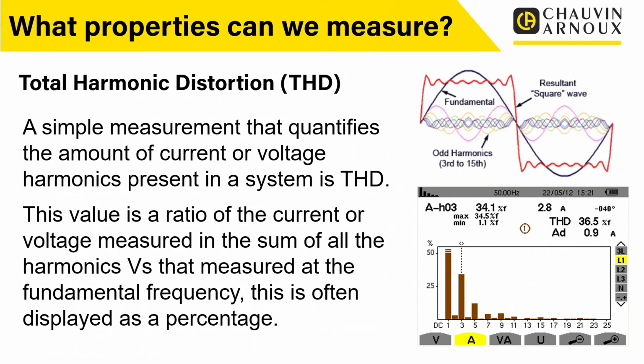And you can see on the graph on the right here, or the display on the right, we're actually measuring current there. So we're talking about current harmonics, and you can see there that we've got quite high 3rd, 5th, 7th, 9th harmonic content in there, and the actual THD is measured there at 36.5%. So that's quite a lot compared to the fundamental. Obviously, if there were no harmonics, we'd want everything to be in the fundamental, no harmonics present, and that is a perfect sine wave again, getting back to where we were.